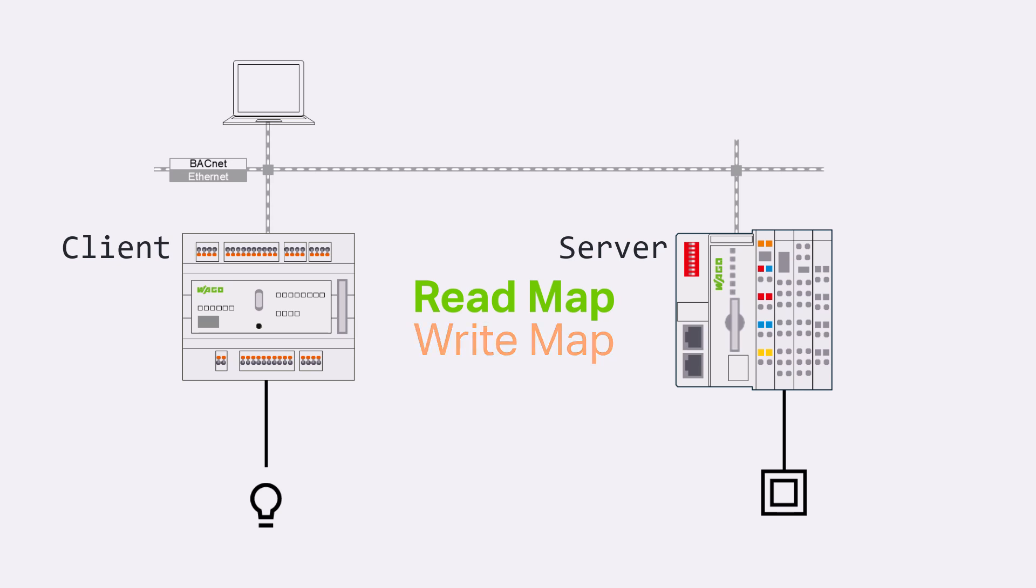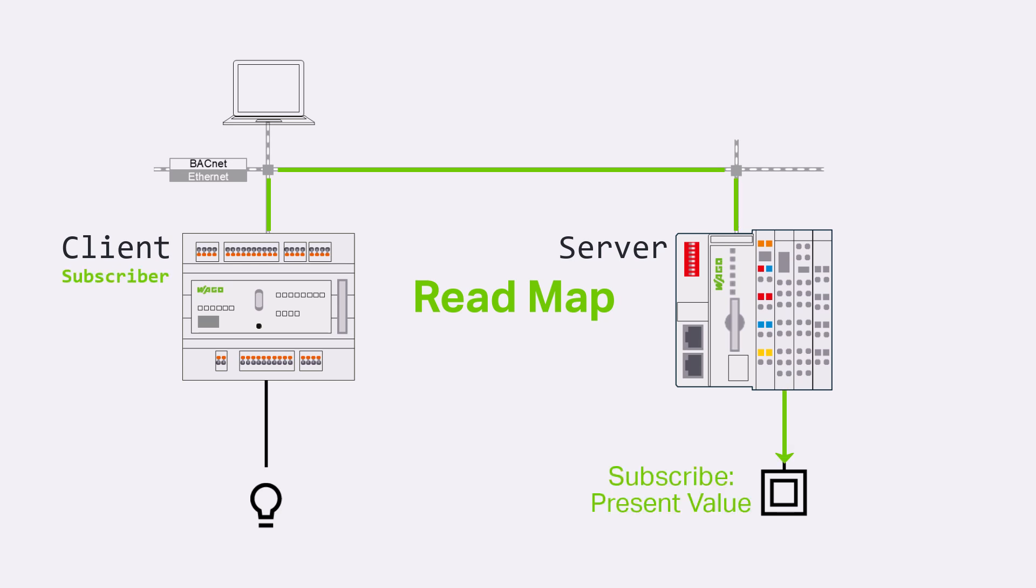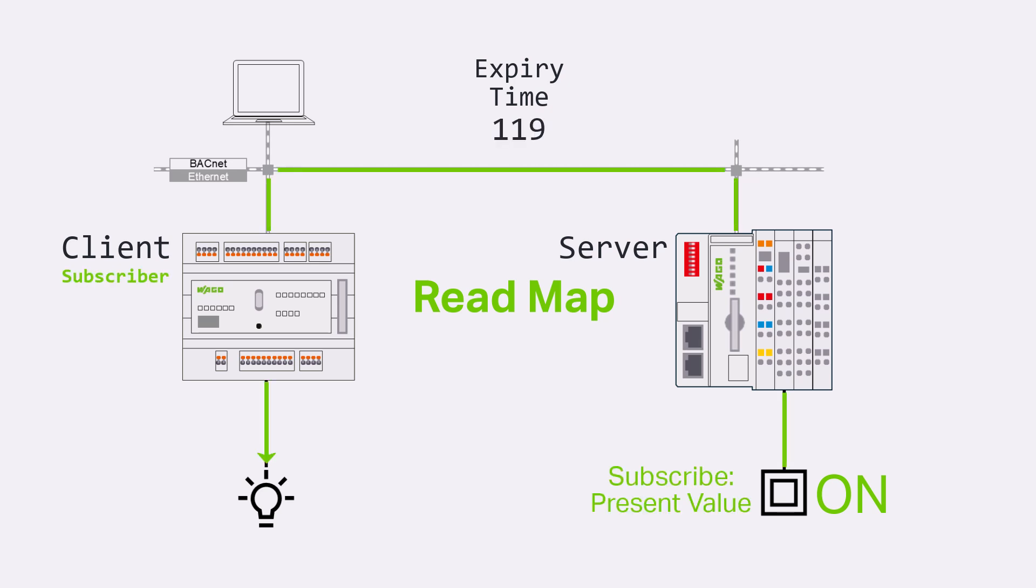With the read function the client initially subscribes to a specific value from the server, making the client a subscriber. When the subscribed value changes, the server sends the value to the client. Additionally, the subscription is only valid for a certain time and is regularly renewed. Due to this system of subscribing, notifying and re-subscribing, the read function is very robust and quickly updated even after a device restart.